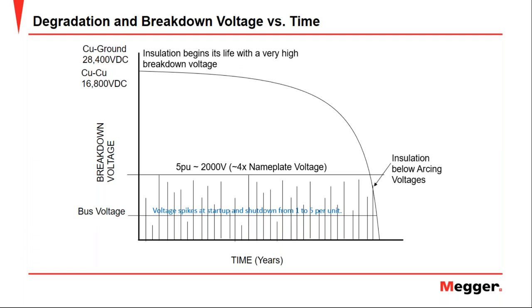Now, as we said before, the low voltage tests are made at or below the nameplate voltage. So this test verifies the state of the insulation in this area. However, this test tells me only if the motor is located above or below the short circuit point, but they don't tell me in which area of the curve the motor is located. That is why they are defined as pass or fail tests.